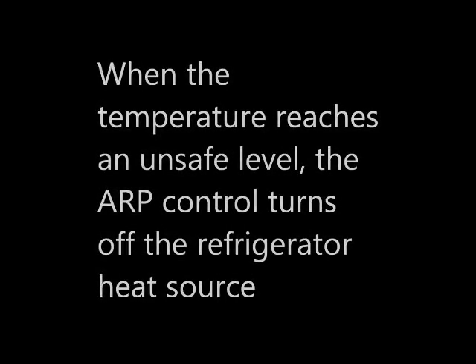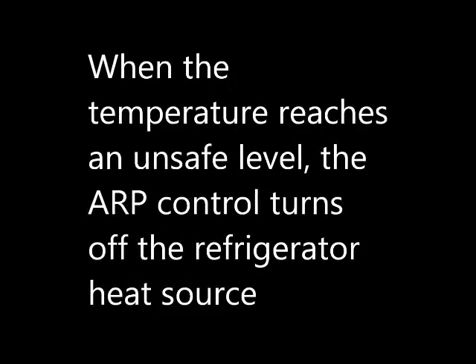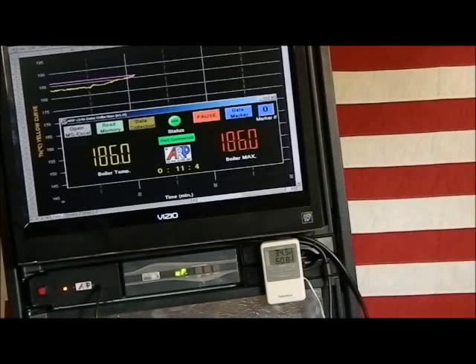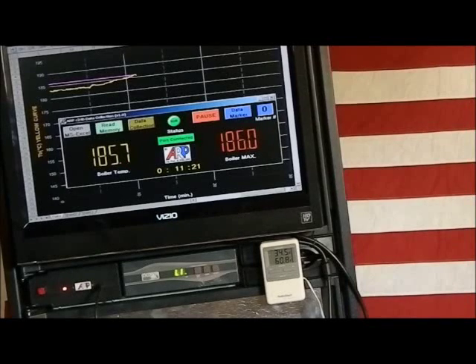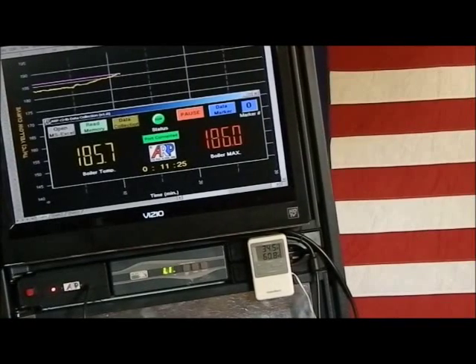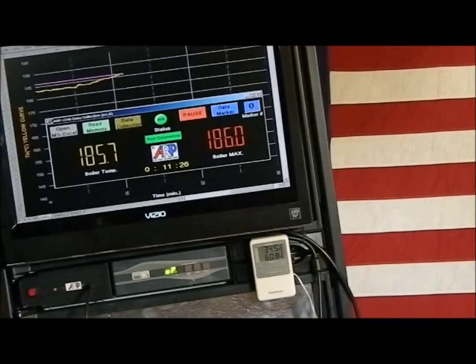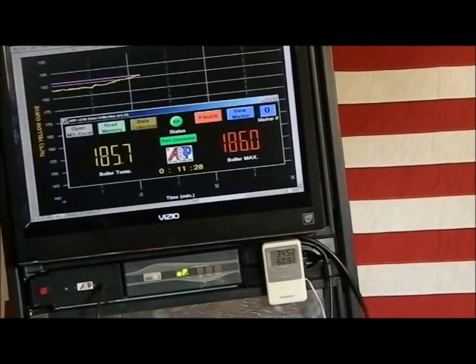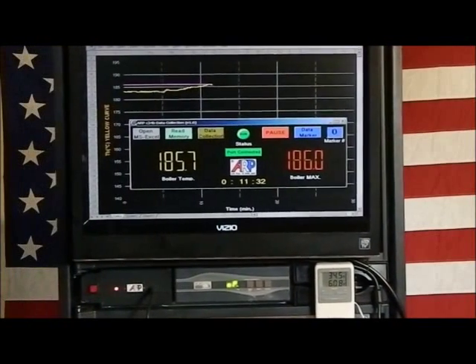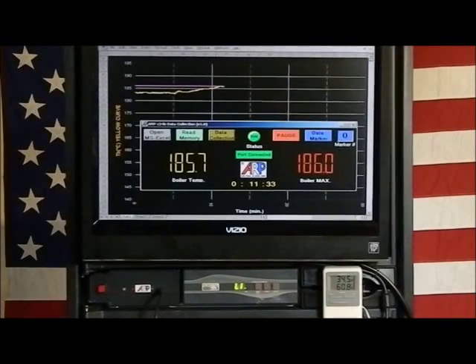When the temperature reaches an unsafe level, the ARP control turns off the refrigerator heat source. Once the ARP control triggers, the green pilot light changes to a flashing red indicator to let the operator know that the ARP control is triggered. In addition, the factory control panel gives an error code and an audible warning.